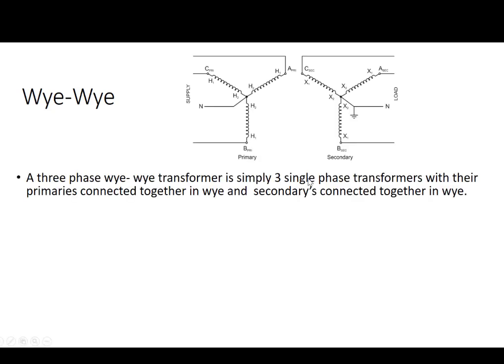Okay, we are continuing with three-phase transformer connections, and we're going to take a look at the first objective from this module, which looks at the first three-phase transformer connection, a YY connection. This YY connection comes basically from three single-phase transformers that are connected to form a Y primary and a Y secondary. The H winding from each single-phase transformer is connected to form the primary Y connection, and the X winding from each single-phase transformer is connected together to form the Y secondary.